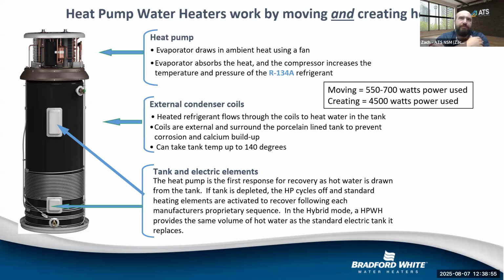Well, and I will comment, vacation mode has become a thing across many manufacturers, and not just heat pumps, but storage type water heaters as well. It's not every water heater, usually it's a selling feature, but it ties into the last part you made, having a plan. Schools started doing this for a while before summer school became more prevalent. When schools would have a 4-month break or a break over Christmas, you would put it into an economy mode and reduce your temperatures, but then that ties into a welcome back: we've got to burn everything off and have a high temp flush. It really does tie into it all in all.